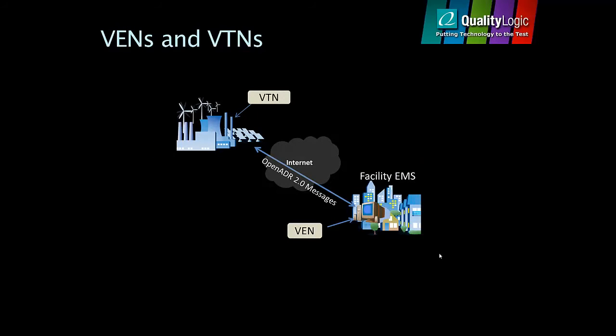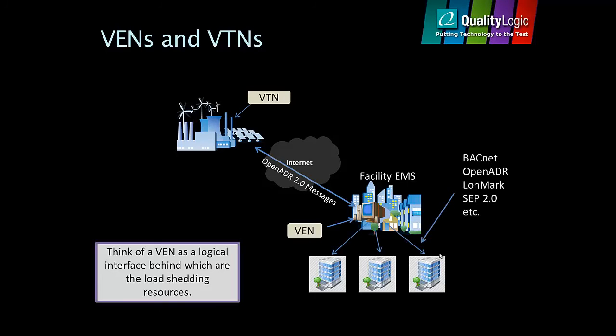From a commercial perspective, the events from the VTN would most likely be directed at a facility energy management system, which would then use BACnet, OpenADR, or other protocols to propagate the event to more granular resources within the facility.